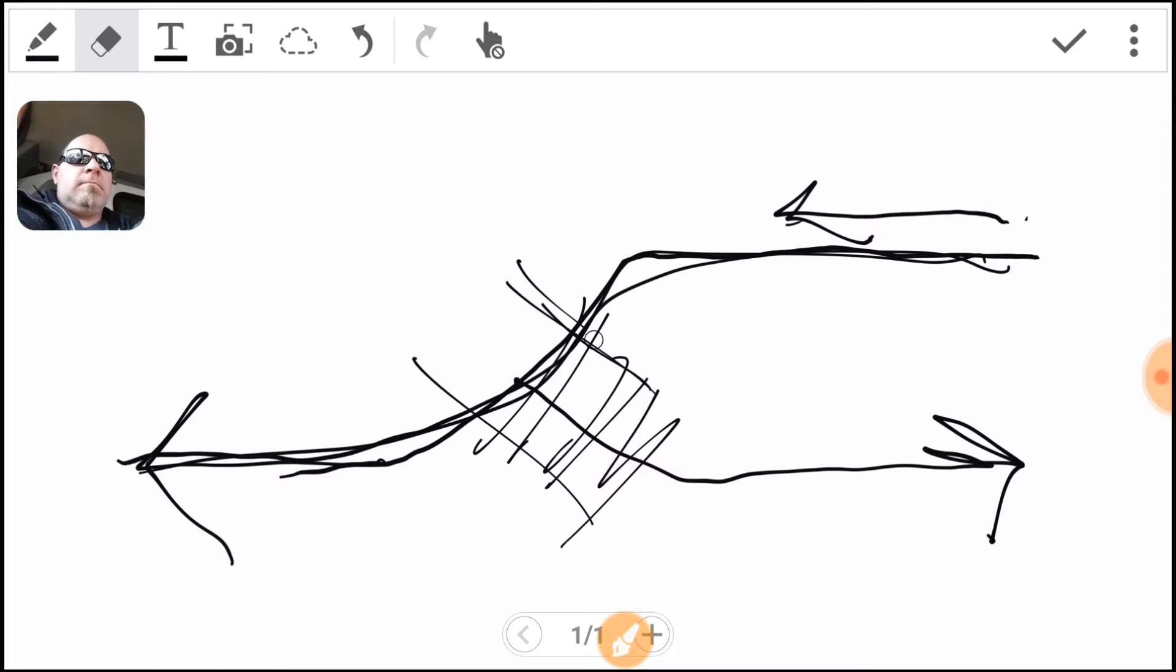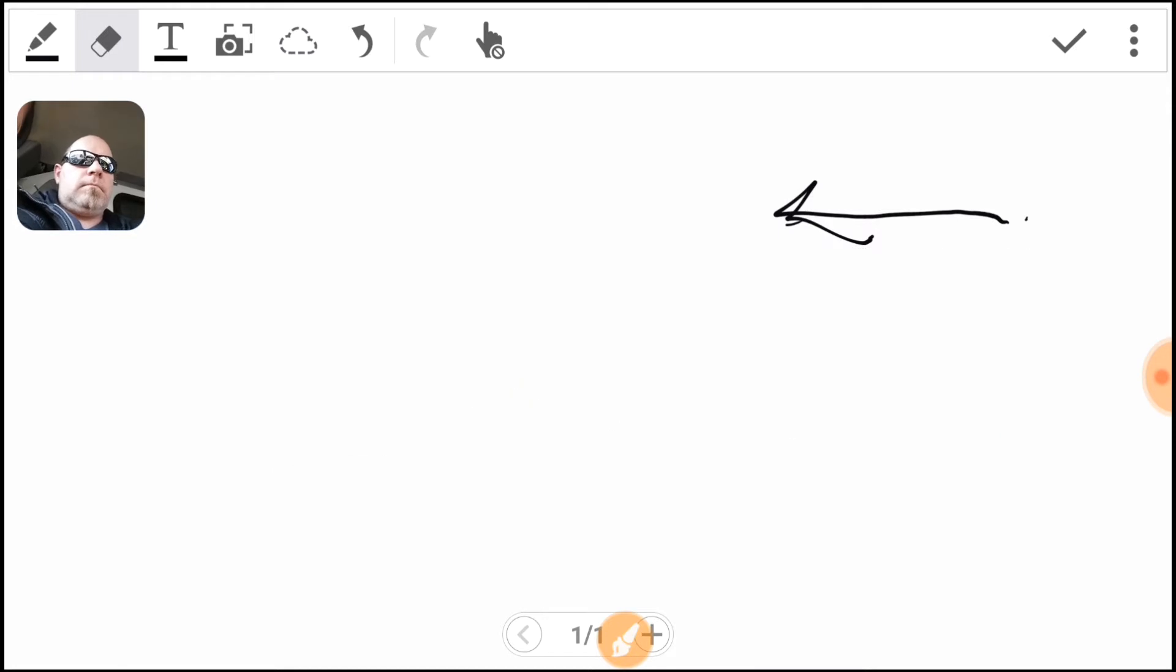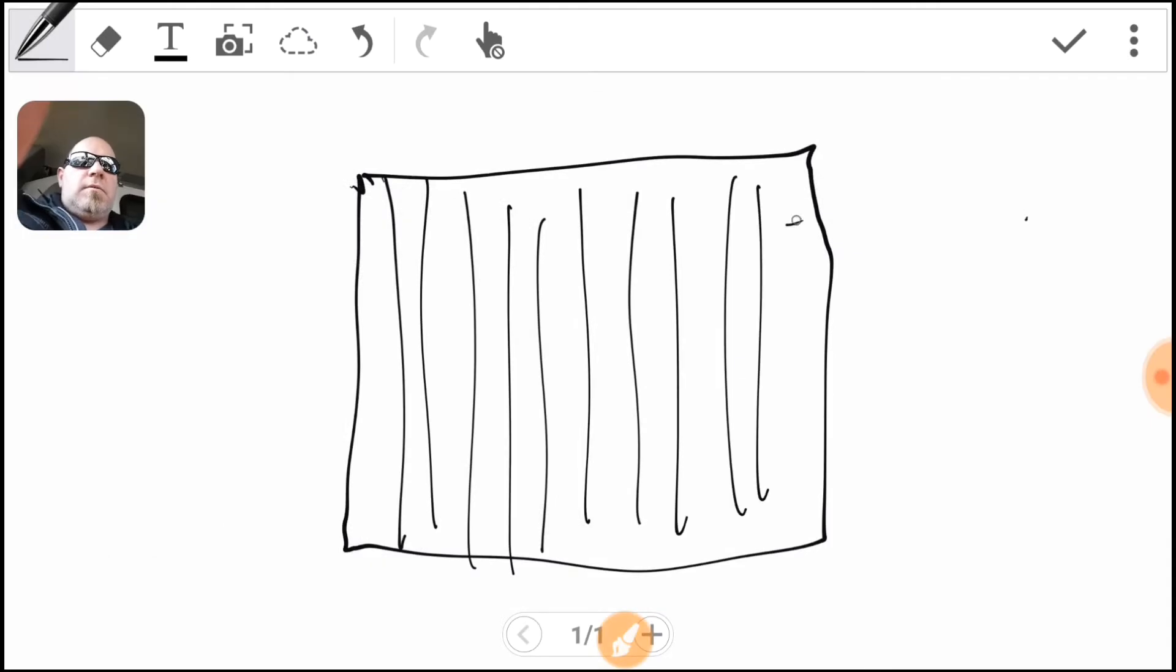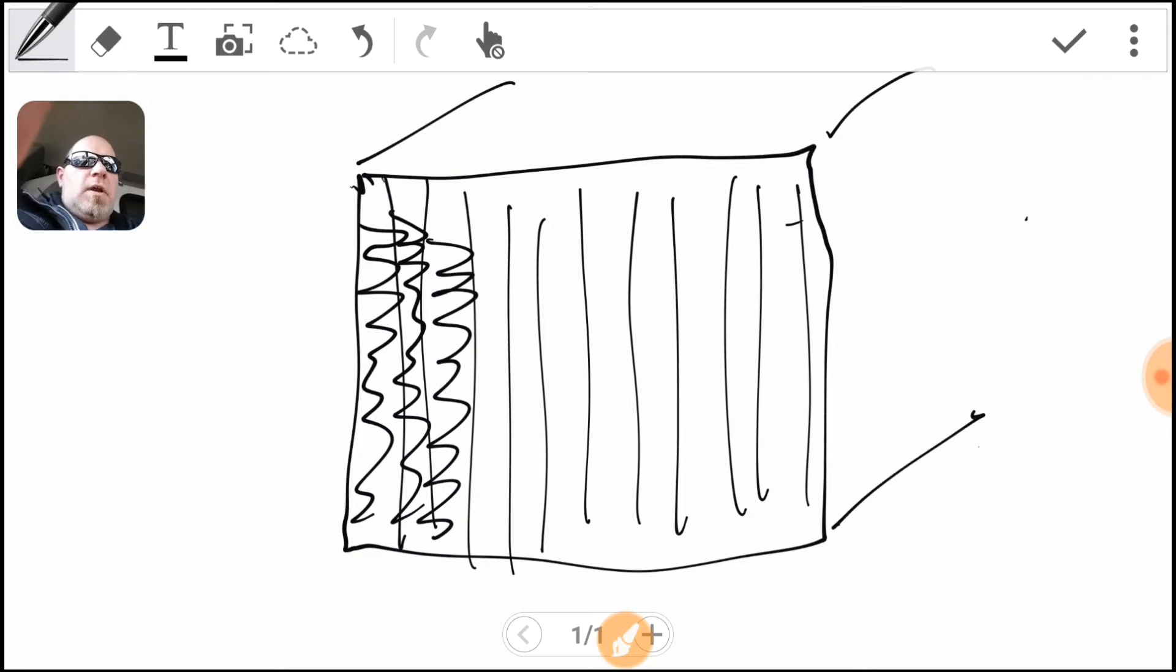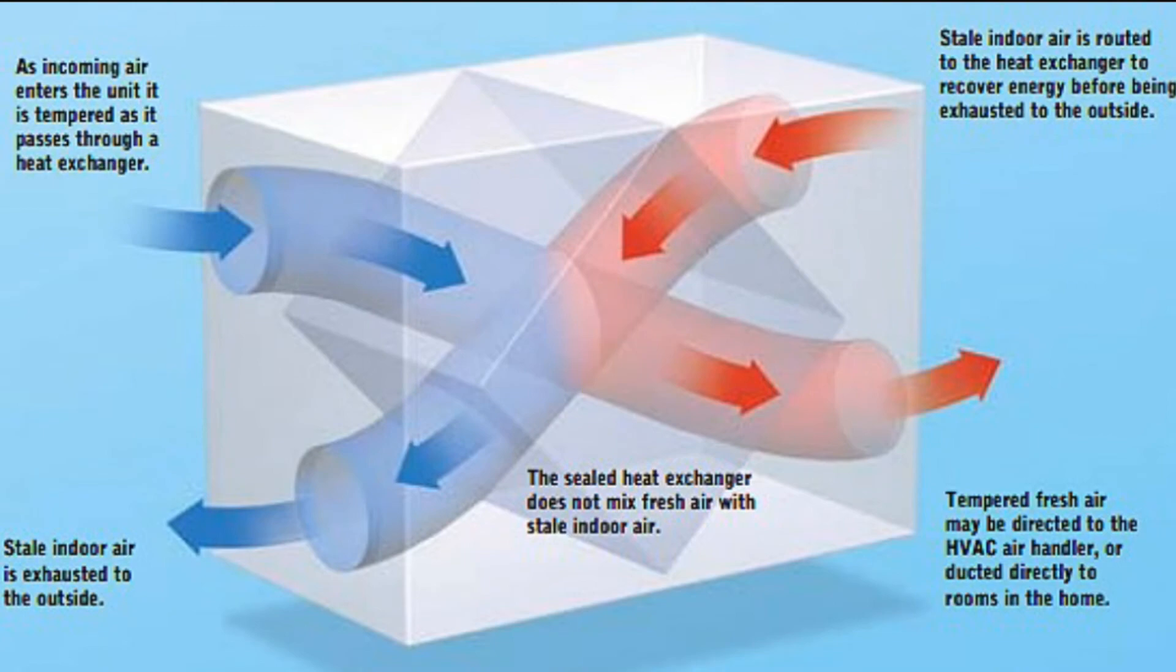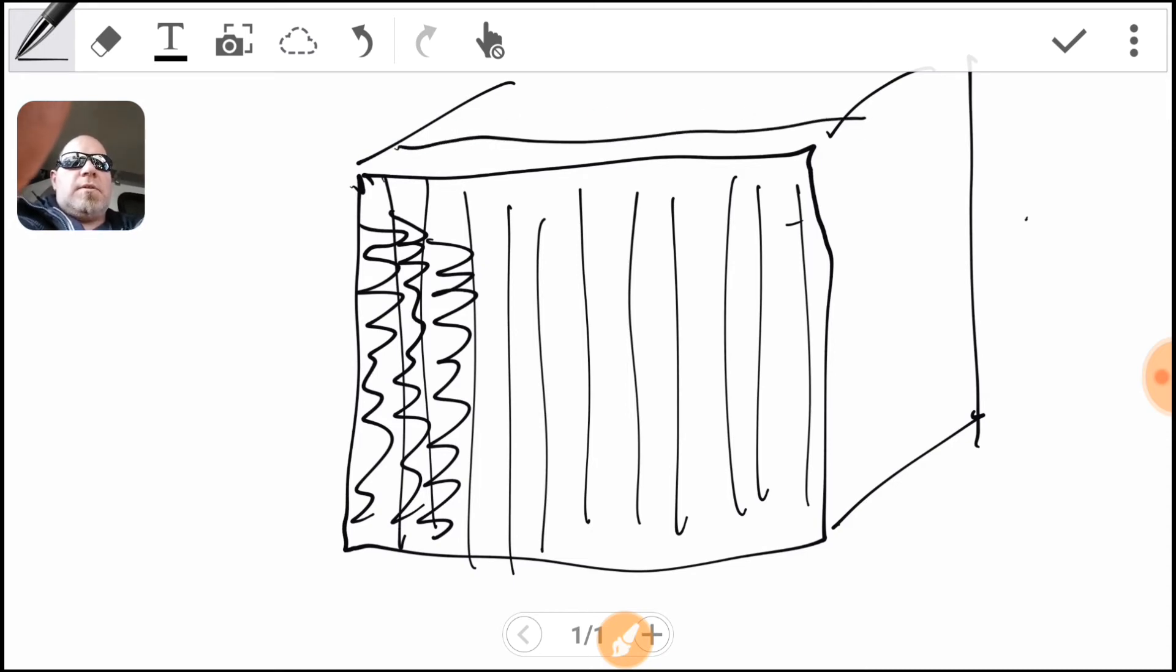Okay, now that media in a heat recovery ventilator basically is a corrugated box. It's a very crude drawing but you know what the edge of cardboard looks like, so it's corrugated so the air can travel through the corrugations this direction and leave. But what it also does is allows the other side of this to be corrugated as well, like so.